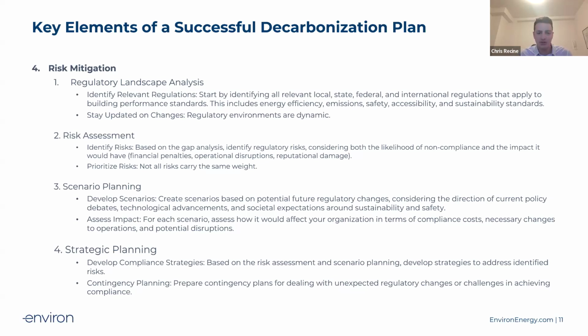Additionally, if you were to move forward with scenario planning, it goes back to that redundancy conversation. If you want to decarbonize, that's great, but there are added layers of N+1 redundancy requirements, generator backup on all emergency power, and the logistics of getting everything in. Many times in healthcare, the building was built around the boiler room or the chiller room, and to access it you have to go through two walls. That's no easy feat with a hospital that cannot shut down. So all that scenario planning and future proofing is required as you think through your master plan.